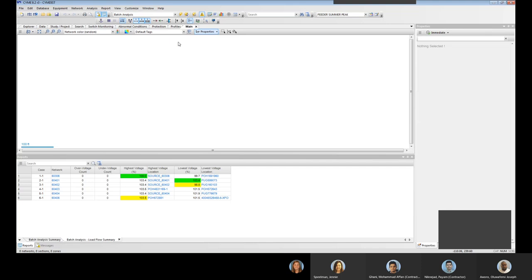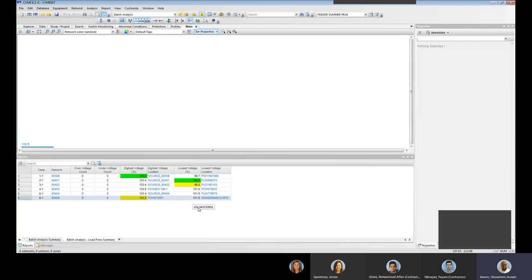Okay, this is just similar to what we do during load flow studies, turning off all the generators because you will be double counting. Most of the loads that are modeled at the load buses, the nodes, are already netted. So the generators are already netted with the load, they've already been like net metered. So turning on the generators for this study will mean double counting the generation, so it's better to turn it off and leave the system as it is. That's the reason you have to turn off generators, because if you leave the generators on you're going to have bad results. It's going to contribute to the voltage as expected.